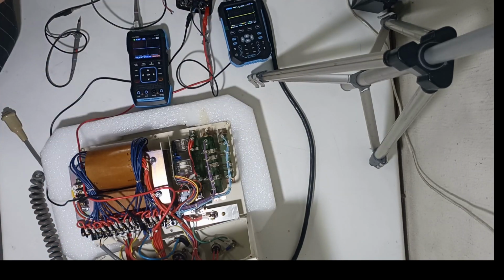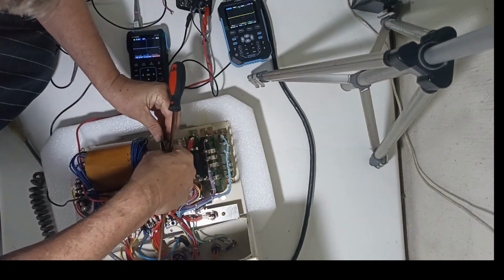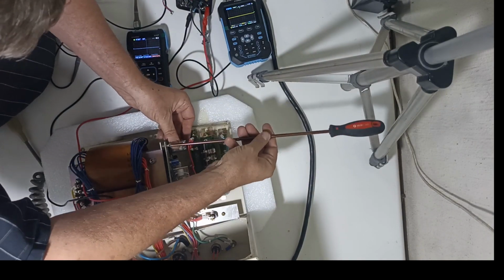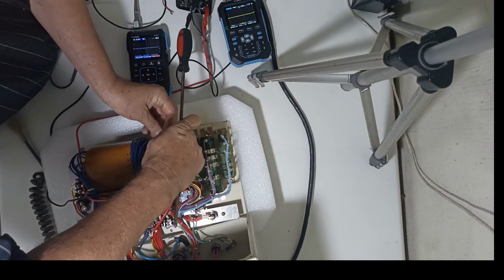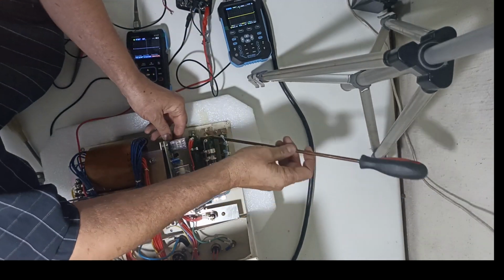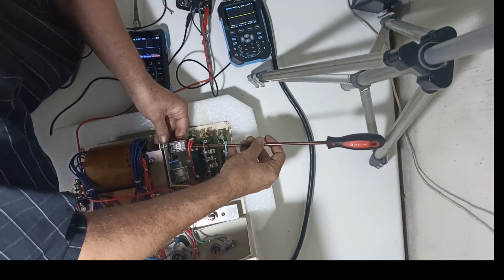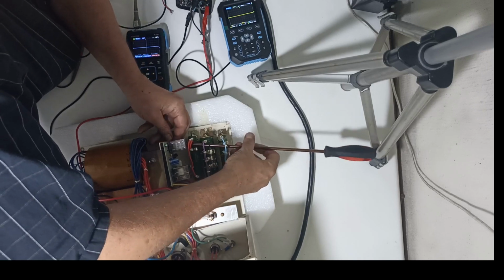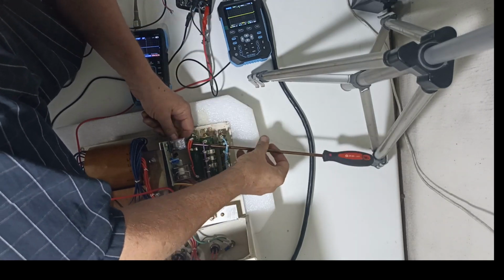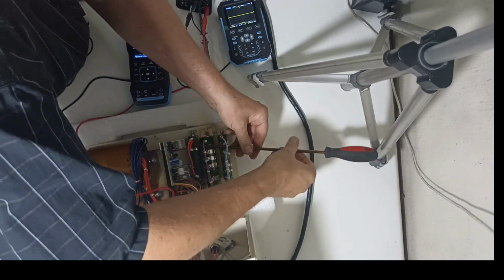And that brings us to the end of part 1 of this project. In the next episode, we will adjust the mA, check the kV, and also verify that the X-ray beam and the light beam are properly aligned so that the photo is taken where the light is shining.